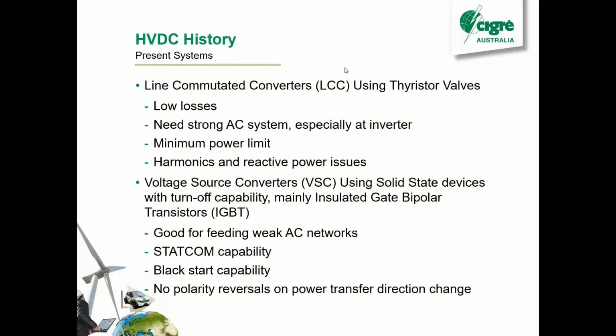And the other thing with the voltage source converter is you don't need to do polarity reversals on your transmission line or cable when you do a power direction change. On LCC you do: the current stays the same and you change the voltage to achieve a power reversal. But on a VSC it's the other way around. The voltage stays the same and you change the direction of the current. So that has some benefits for cables, especially XLPE cables. XLPE cables don't like polarity reversals. So generally if you have an LCC link, you have to go with the older mass impregnated, the oil cables, so paper oil, lead sheath sort of thing, and they can handle the polarity reversals, whereas the XLPE can't.